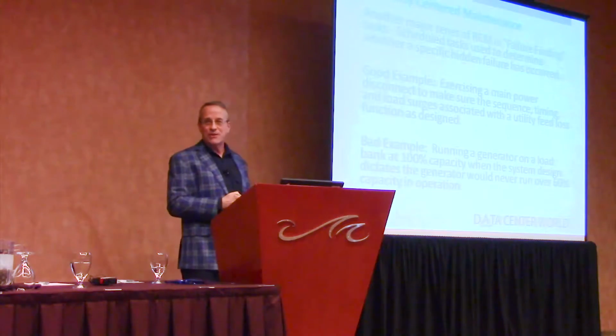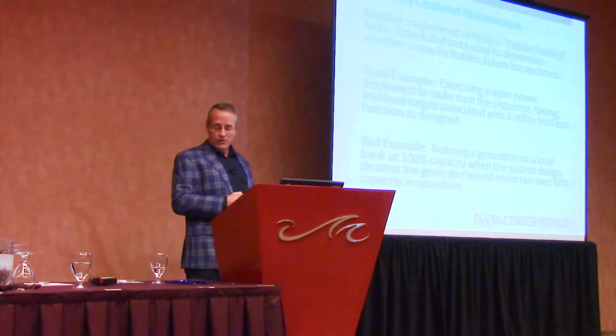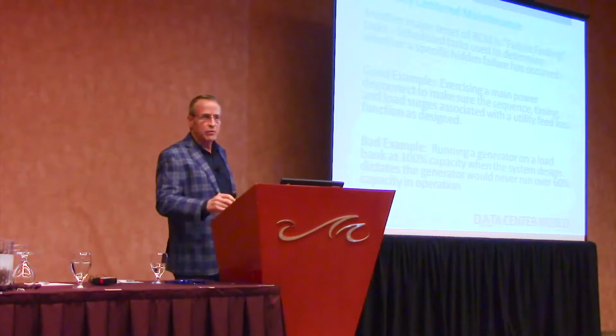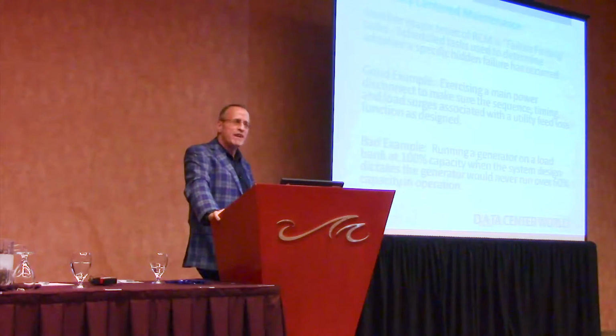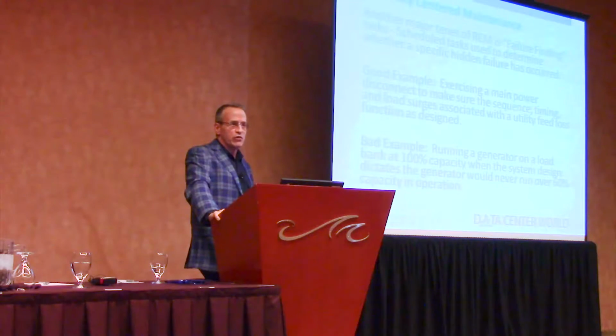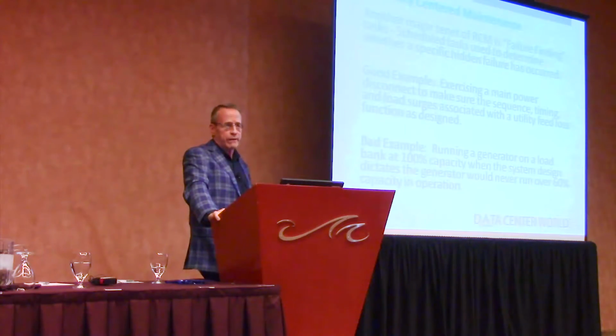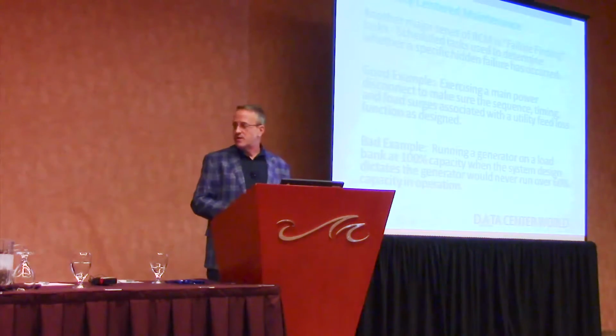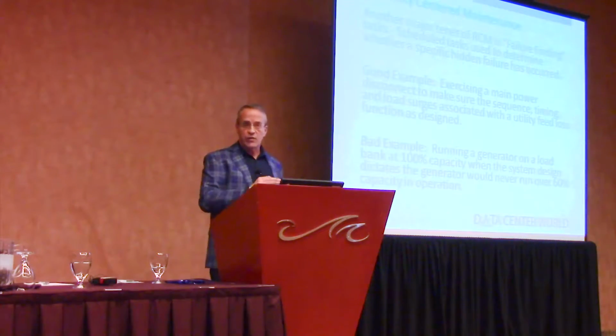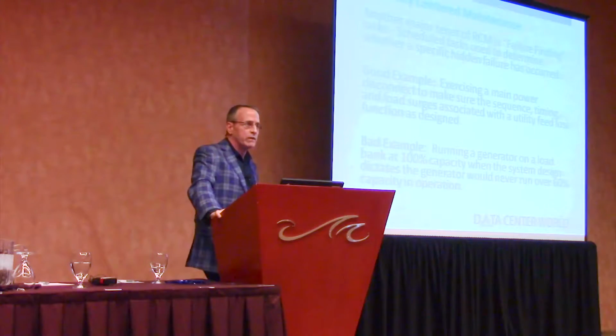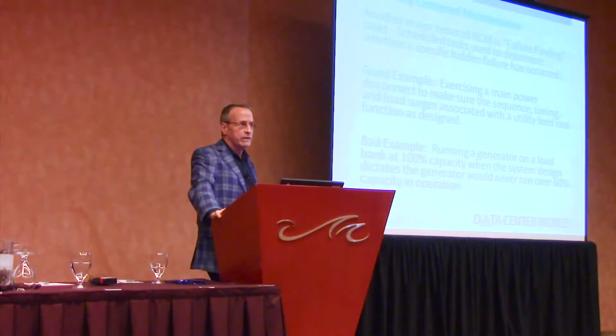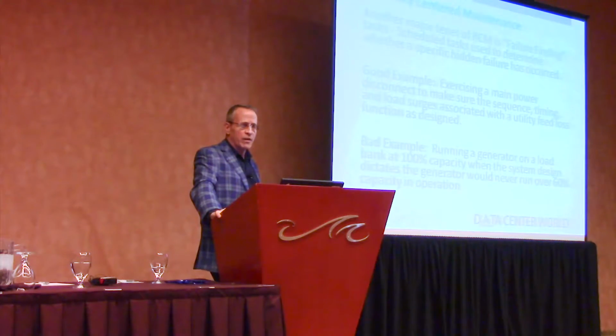So people have come to accept our 10 a.m. thing. Another failure finding thing is connecting that load bank. In our scenario, if we fail over a generator, its utilization goes from 30-40% to a maximum of 60%. In a worst case failover situation, our generators will never run at over 60%. We can talk about generator glazing another time; it has not been an issue in our 15-year history. So if that generator is never going to run at over 60%, why would I connect it to a load bank and run it at 100%? So I can spin the bearings, stretch the rods, and have a blowout?